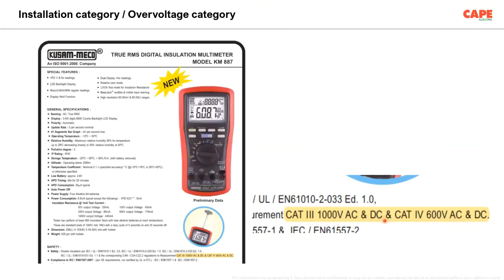What does this mean is, you can use this meter if the operating voltage is up to 1000 volt in a category 3 location, that means not at the main distribution board, not at the point of commencement of supply. After the point of commencement of supply, you can use this meter up to 1000 volt AC and DC. At the point of commencement of supply, you can use it up to 600 volt AC and DC.